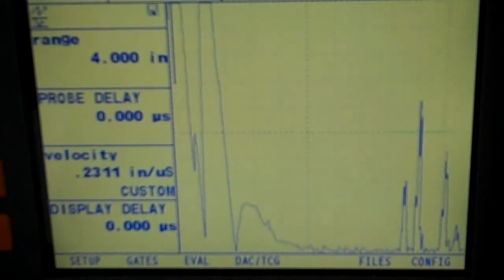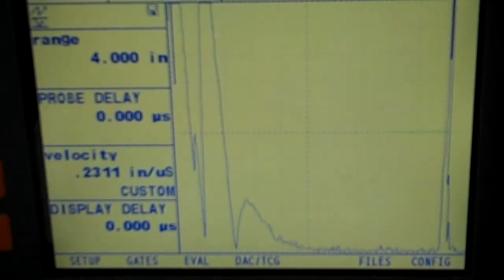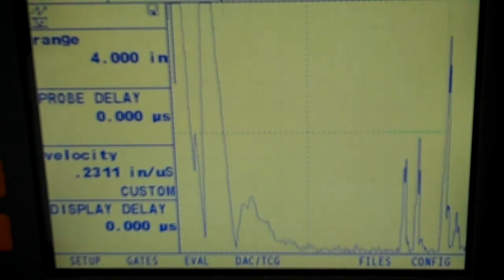So I'm going to move my transducer over the top of that notch and step and the 4-inch range all at the same time. When I did that, it took me to a screen that looked like this. If I just go back to the 4-inch signal, there's my 4-inch signal coming right up at 100%. Then I come back to the notch and the step, and that's what we see right there. If we get a little more goop, there we go, right there. Now we have our 4-inch signal, a signal at 90%, and then a signal at about 85%.